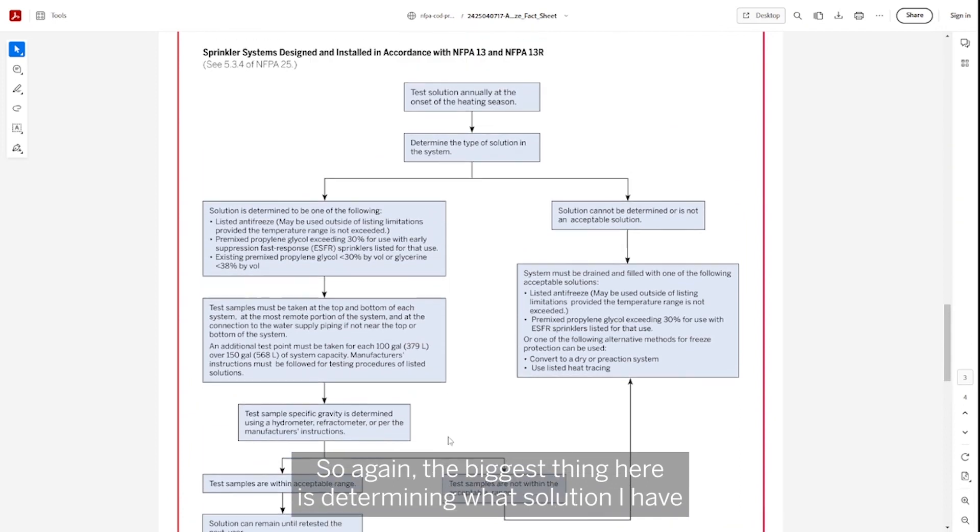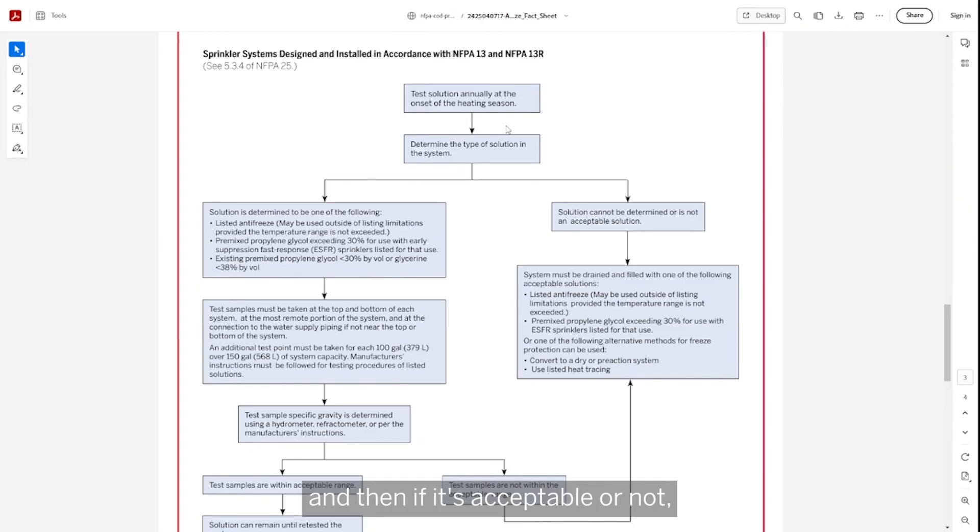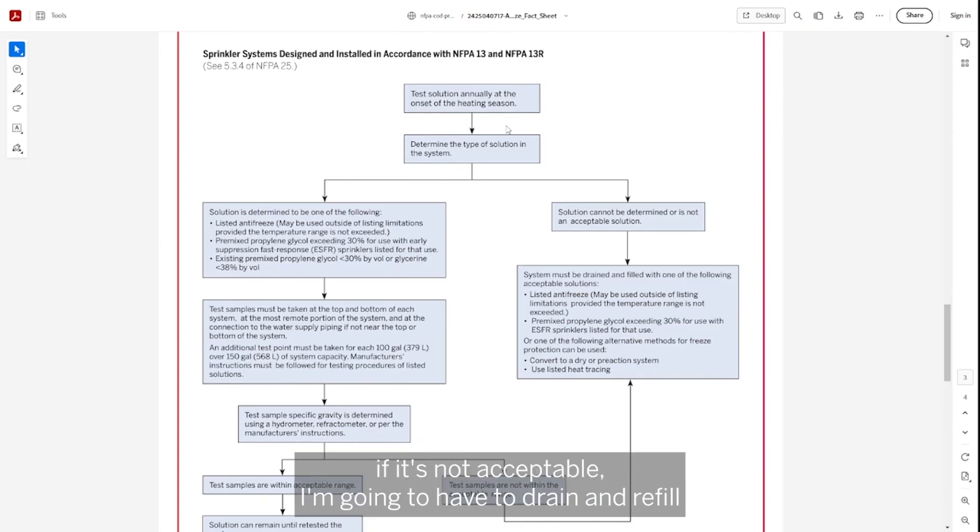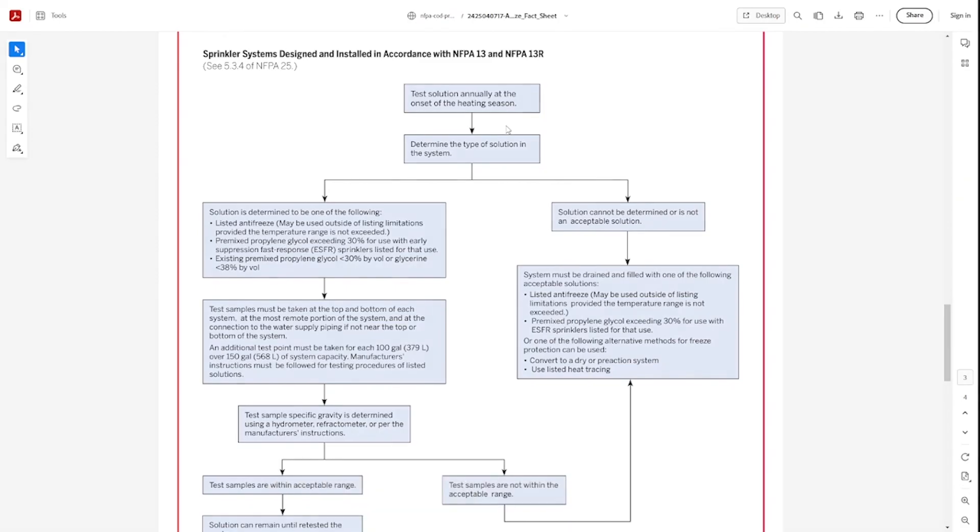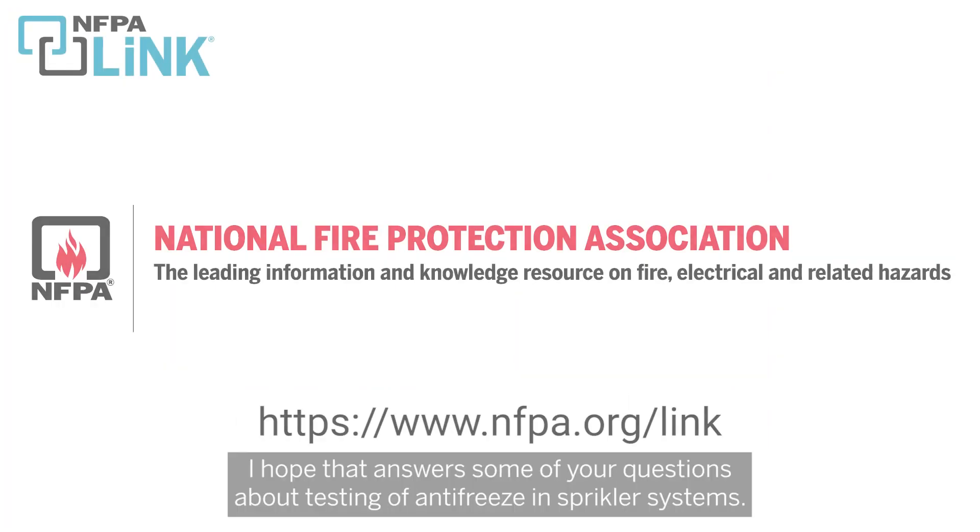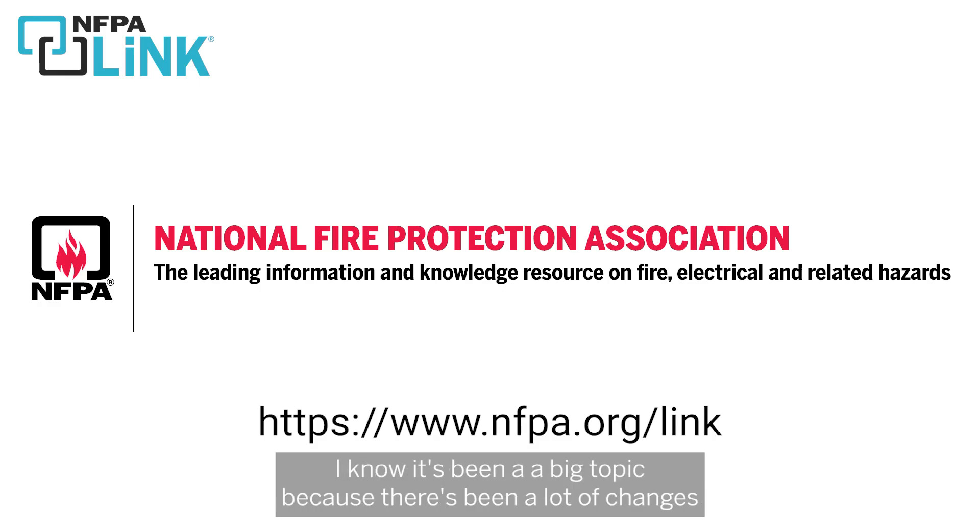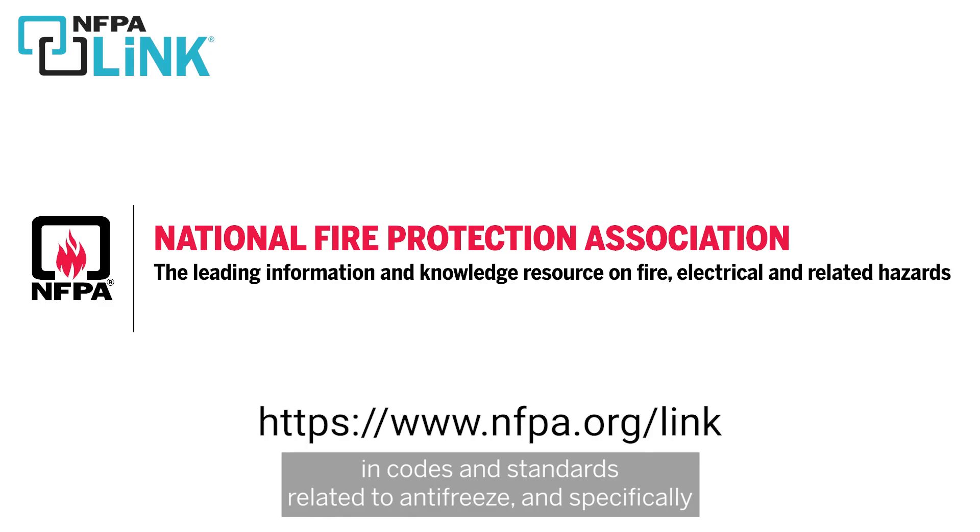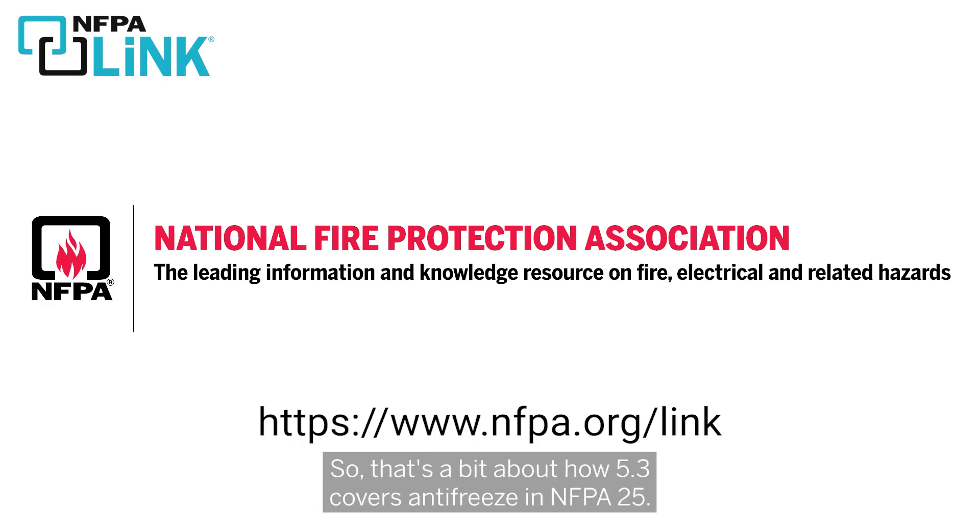So again, the biggest thing here is determining what solution I have and then if it's acceptable or not. If it's not acceptable, I'm going to have to drain and refill with an acceptable solution or try to convert to something different. I hope that answers some of your questions about testing of antifreeze in sprinkler systems. I know it's been a big topic because there's been a lot of changes in codes and standards related to antifreeze and specifically the introduction of listed antifreeze solutions into the market.